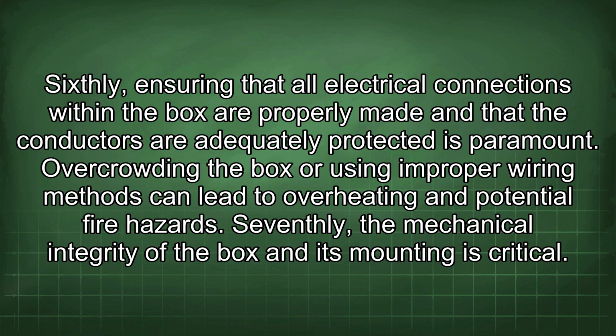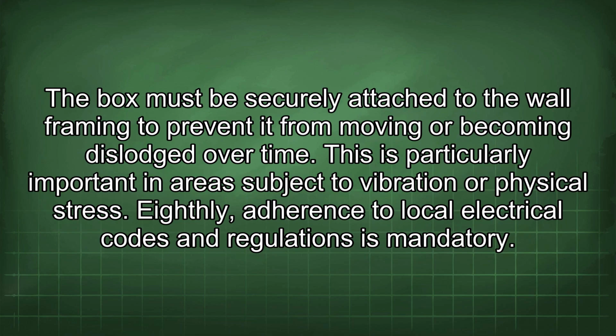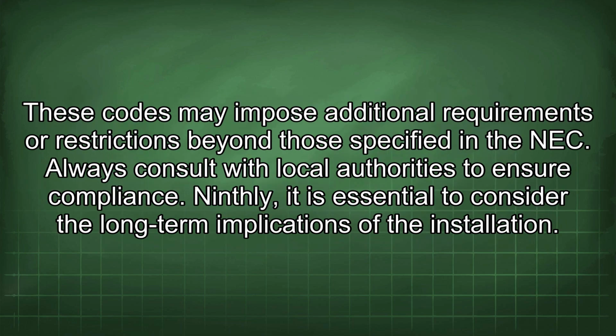Seventhly, the mechanical integrity of the box and its mounting is critical. The box must be securely attached to the wall framing to prevent it from moving or becoming dislodged over time. This is particularly important in areas subject to vibration or physical stress. Eighthly, adherence to local electrical codes and regulations is mandatory. These codes may impose additional requirements or restrictions beyond those specified in the NEC.